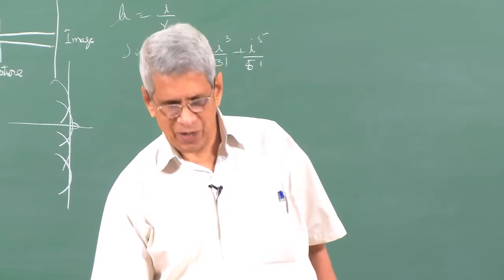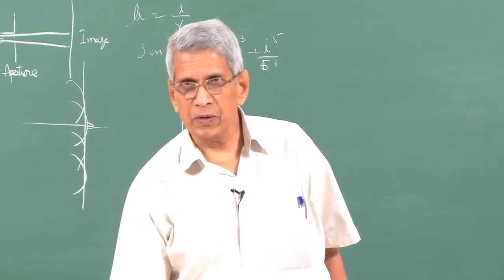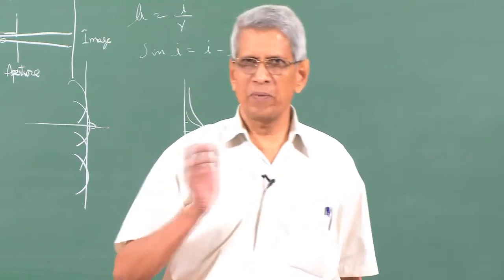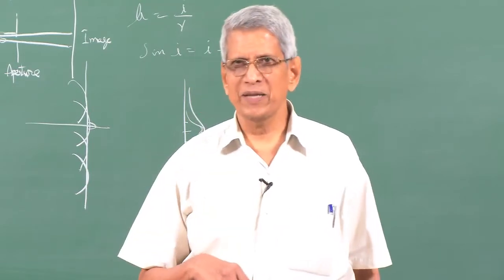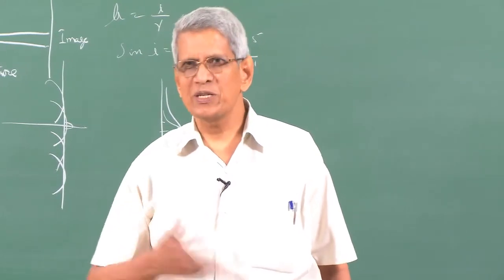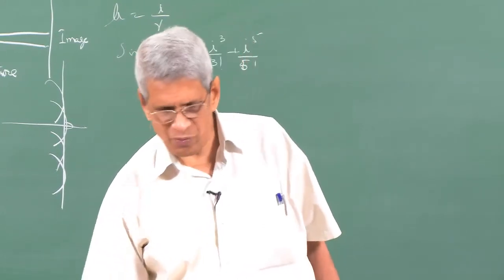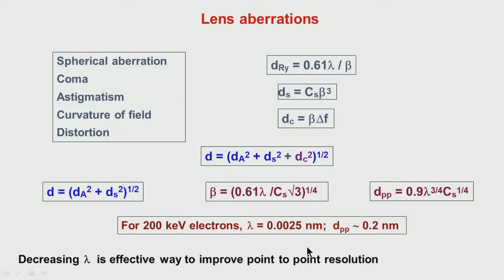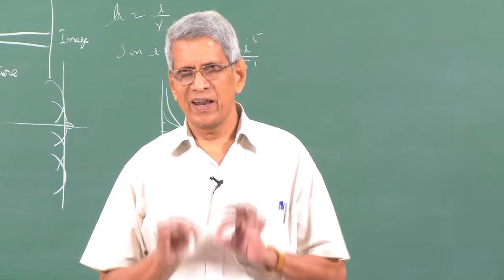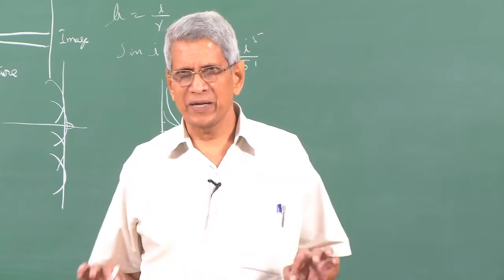To improve resolution, one can decrease lambda — this led to the development of high-voltage microscopes operating at 1, 2, or 3 million volts. Alternatively, the spherical aberration coefficient Cs can be reduced at normal operating voltage — these are called aberration-corrected microscopes. We have now covered how to calculate resolution for a lens with aberrations.